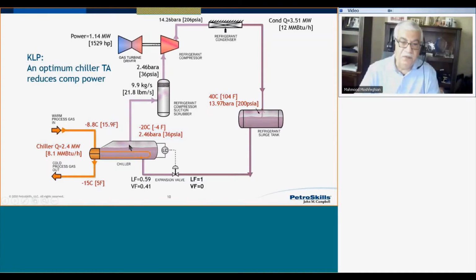Again, what's the impact of this approach temperature here? If I use a lower approach temperature, my chiller temperature would be higher, and my compressor power is going to be less. So here's another point where we can utilize approach temperature to minimize the power requirement of my compressor. But keep in mind, when we go to a low approach temperature, we have to make sure we choose the right type of heat exchanger. Each type of heat exchanger has some limitation on the minimum approach temperature.